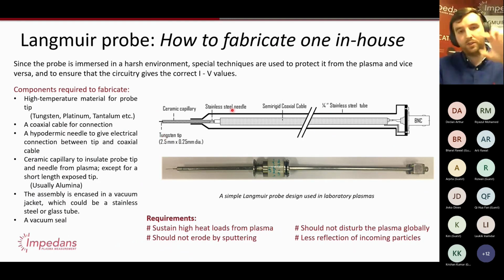Also, in general, you want to taper down from where you go from the shaft to where you have the probe, because this shaft can perturb the plasma. But plasmas have a property that they're self-shielding over a distance of several Debye lengths, which is something this measures. So the idea is that you start off with your thick shaft, but you taper down and taper down and taper down, so that by the time you get to the tip, there's minimal perturbation in the area where the tip is actually sensing. Okay? There are some other considerations.